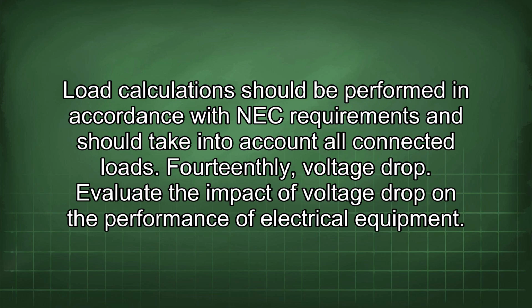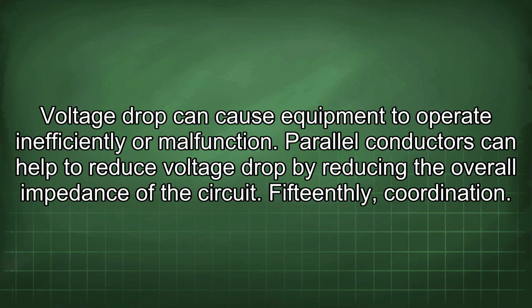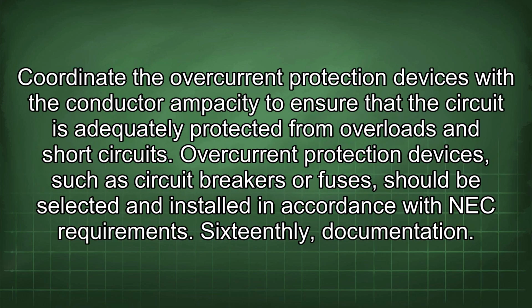Evaluate the impact of voltage drop on the performance of electrical equipment. Voltage drop can cause equipment to operate inefficiently or malfunction. Parallel conductors can help to reduce voltage drop by reducing the overall impedance of the circuit. 15th, coordination. Coordinate the overcurrent protection devices with the conductor ampacity to ensure that the circuit is adequately protected from overloads and short circuits. Overcurrent protection devices, such as circuit breakers or fuses, should be selected and installed in accordance with NEC requirements. 16th, documentation.